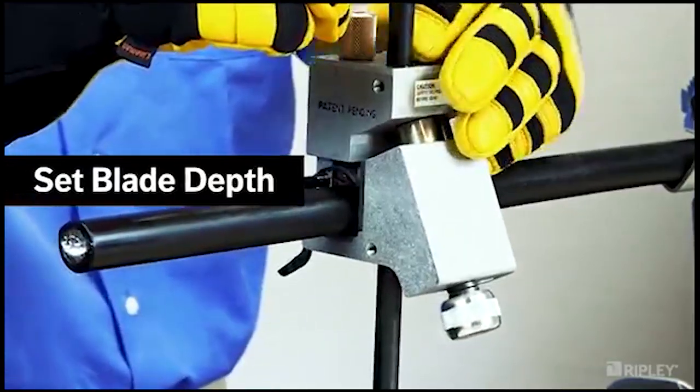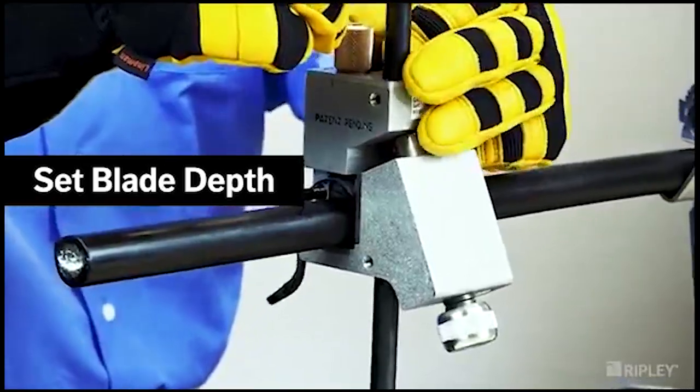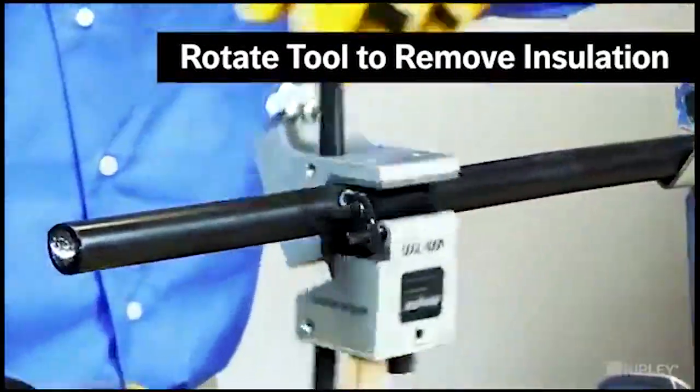Adjust the blade angle to 0 degrees for a squared edge and slowly adjust the blade depth down to the conductor. Rotate the tool to remove a channel of insulation to expose the conductor.